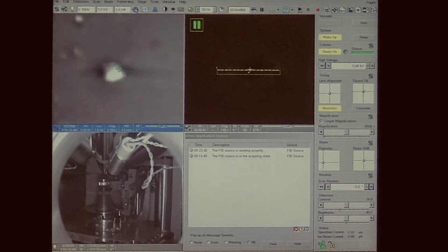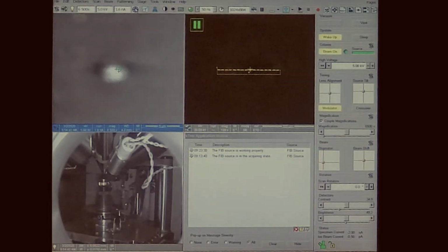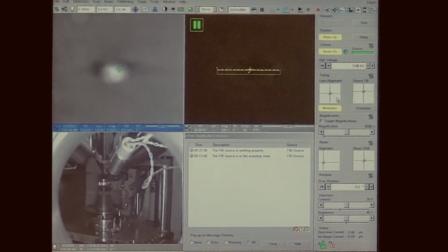So you click that, and what you ideally want to see is the image going just in and out of focus. No movement at the center, or no lateral movement at the center. Here you can see there's not much, but there's a little bit of vertical movement. So I'm simply going to come over here to the lens alignment box, just like all the others. I can reduce it by axis or go for full freedom. Again, on this one, I tend to prefer to go by axis.